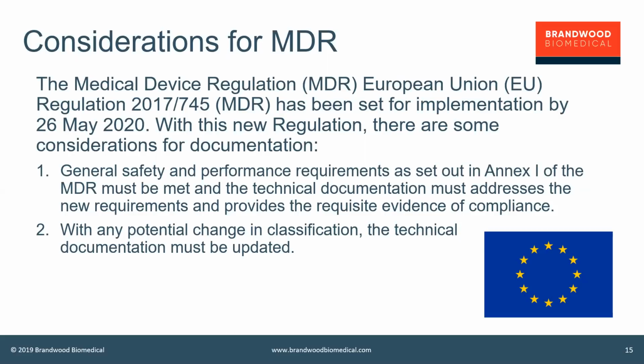Now, that means that when you actually have to do the regulatory pathways, it does create some friction between the two pathways. So Australia, for instance, you will need to really consider how you're going to apply, given that it's not the same classification and that your CE mark is for a different classification of device. But your technical file will be supportive of wherever you're going to go, because you basically played to the most risk, the highest classification, and by creating that technical file in such a manner, all of the lower classification areas will be addressed.